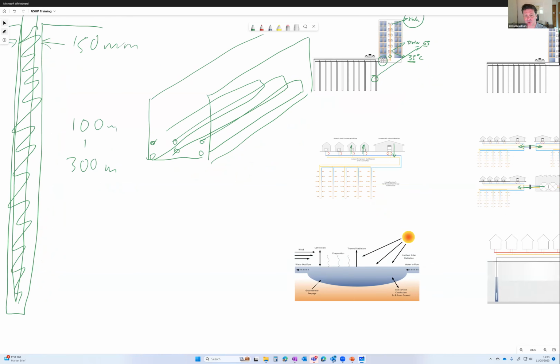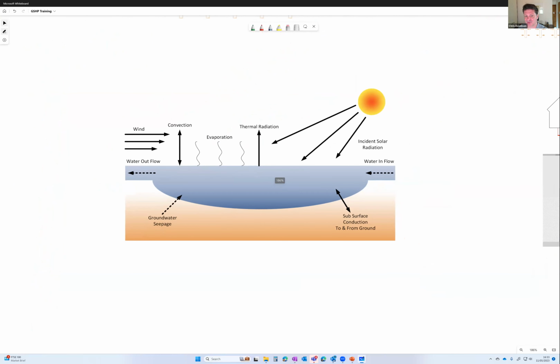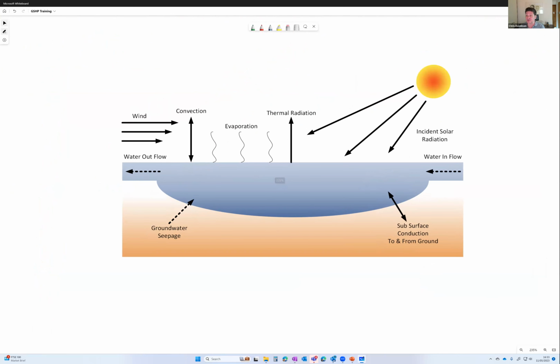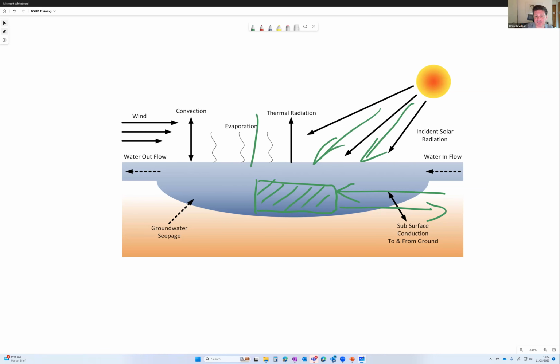There is one other type of closed loop system that's very much worth talking about, which is when we've got some surface water. We can install a heat exchanger in a body of surface water, and take heat out of it and put heat back into it. Provided we are balancing what we're doing to the lake with the natural gains and losses of heat that occur, then we've got a sustainable system again. Our main gains are via solar gain, and our main losses are actually via evaporation off of that lake.